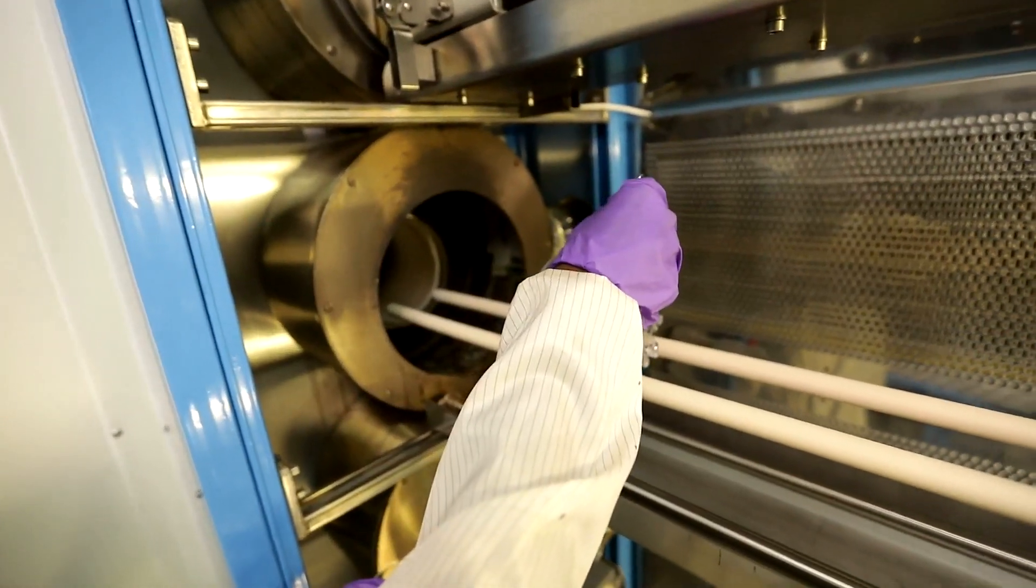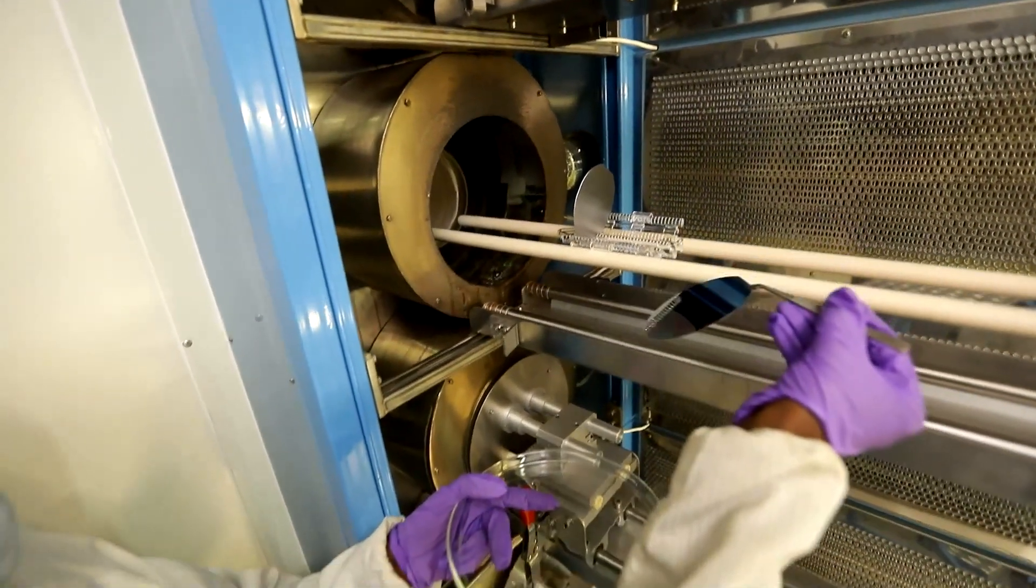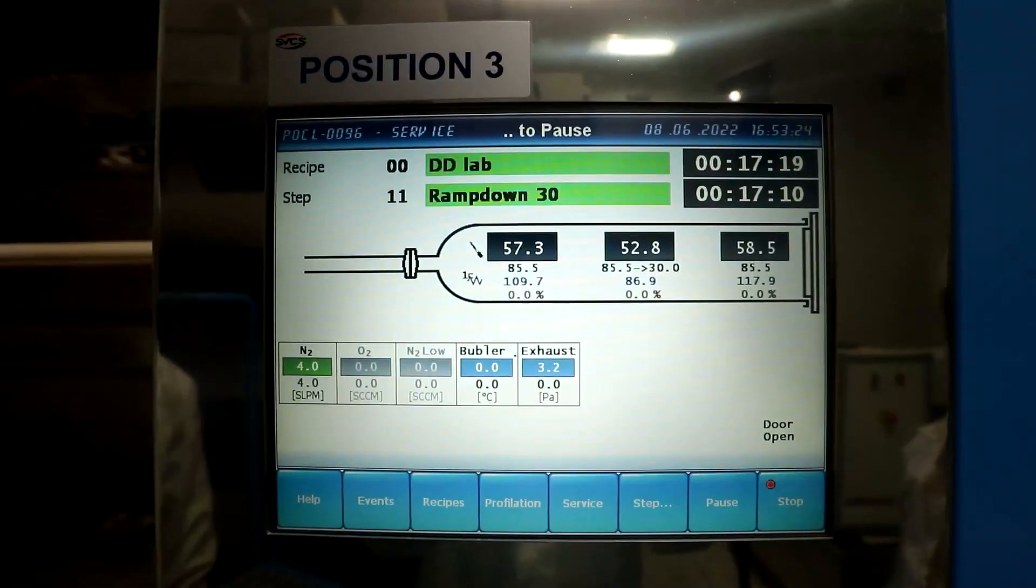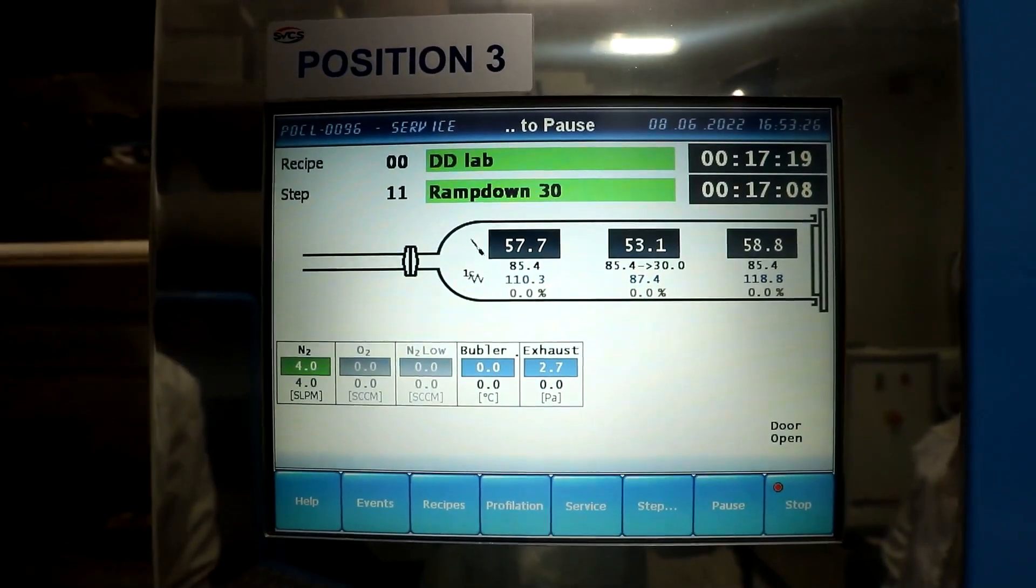Next we will bring down the temperature to 30 degrees Celsius. It will take around two hours. At the end of the process, close the processing window and turn off the breaker. Close the gas lines and switch off the chiller and exhaust.